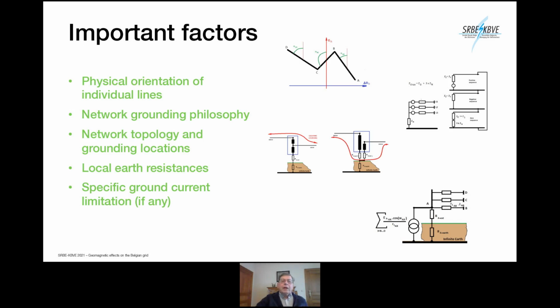On the figure at the top right, you see the equivalent of the earthing scheme for a single phase fault. You see that there is the neutral point resistance you put in every node. The neutral point resistance, in fact, influences the zero sequence impedance of the network. That's for the alternating current part. But the neutral point resistance, as mentioned on the slides before, and as you also see on the slide at the bottom, also influences the ground currents from geomagnetic origin. And this is important, particularly in Belgium. We come to that later.